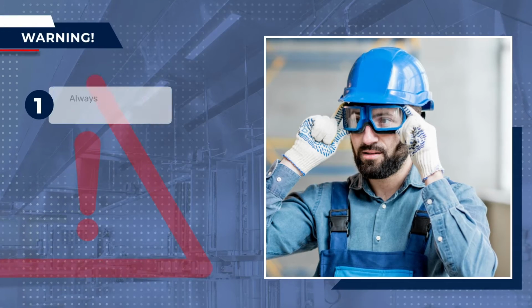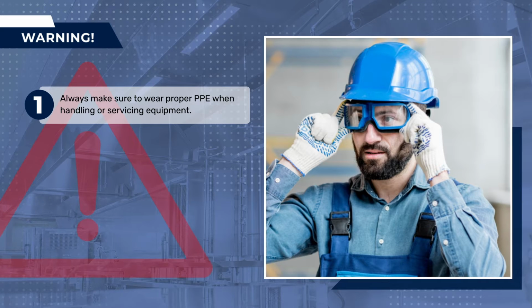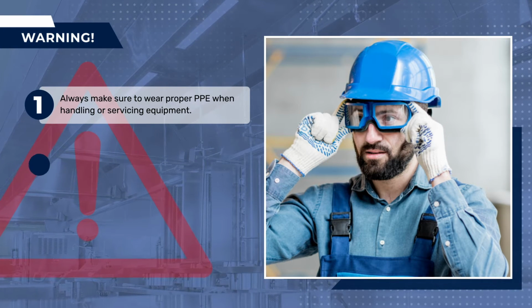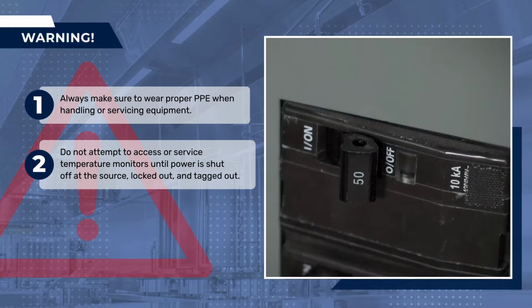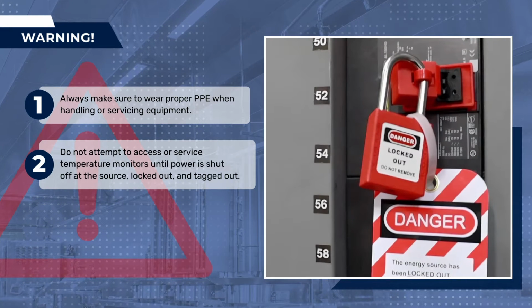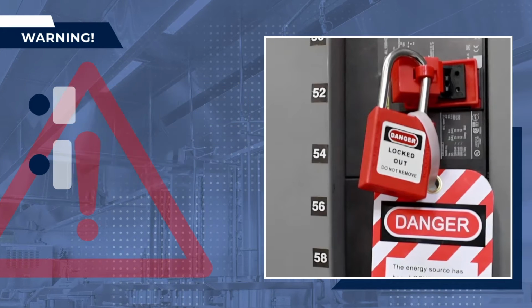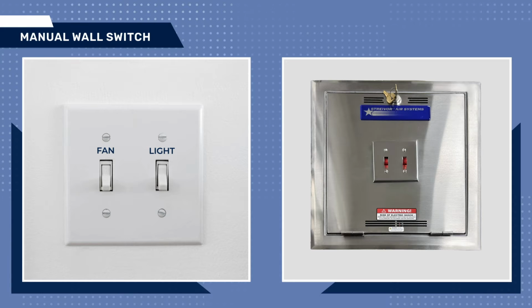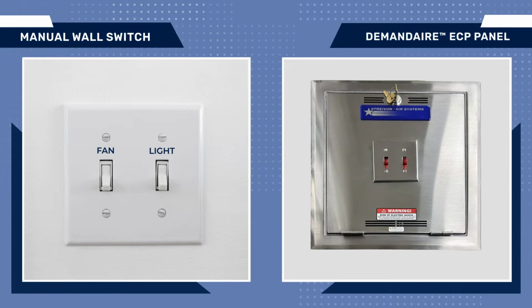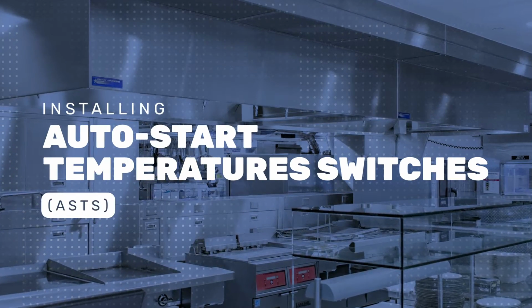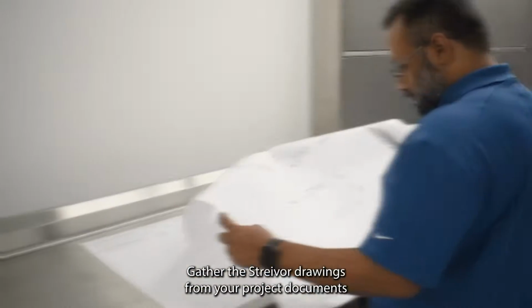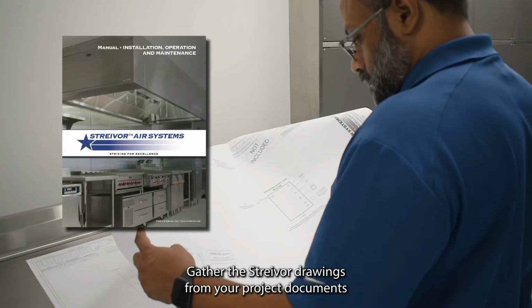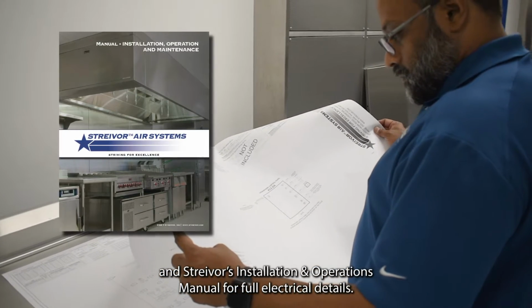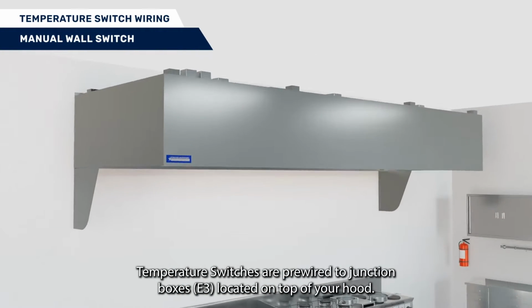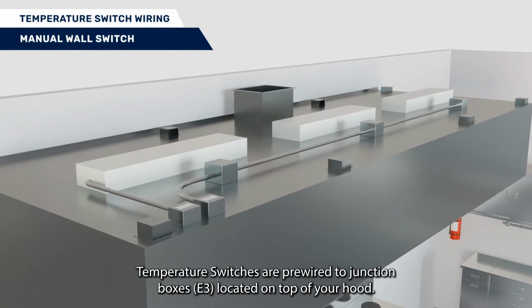switches. Warning: always make sure to wear proper PPE when handling or servicing equipment. Do not attempt to access or service temperature sensors until power is shut off at the source, locked out, and tagged out. The temperature switches can either be connected to a manual switch or to a Streivor DemandAire panel during installation. Gather the Streivor drawings from your project documents and Streivor's installation and operations manual for full electrical details. Temperature switches are pre-wired to junction boxes, E3, located on top of your hood.